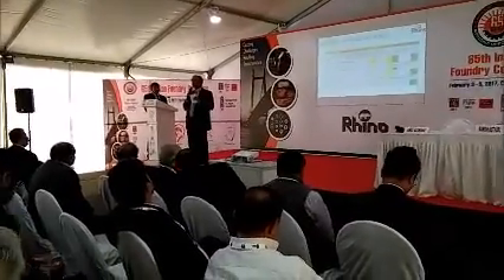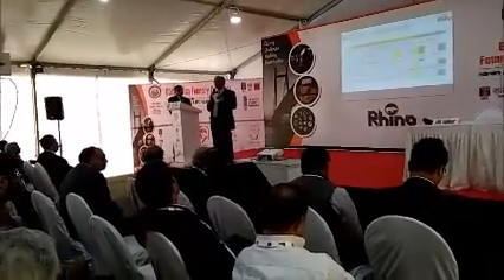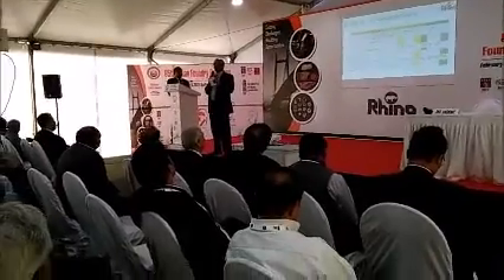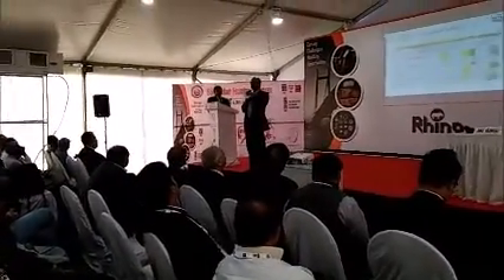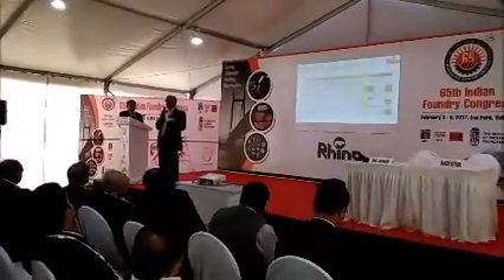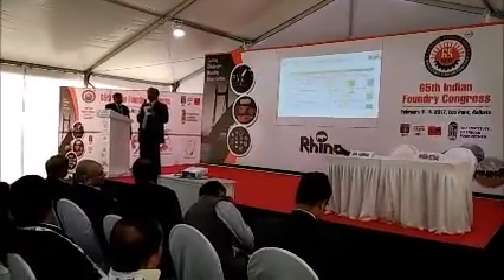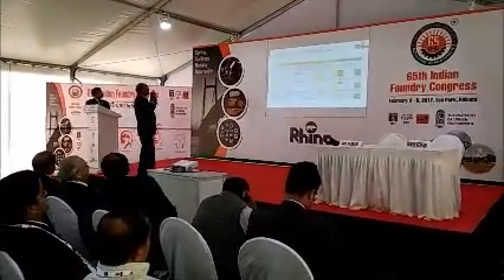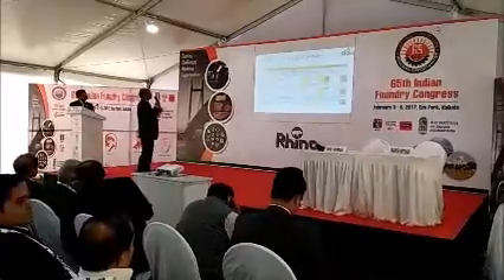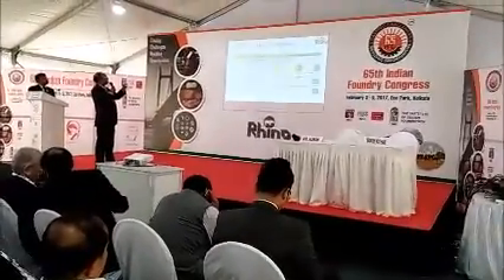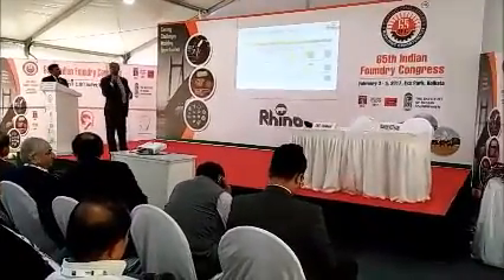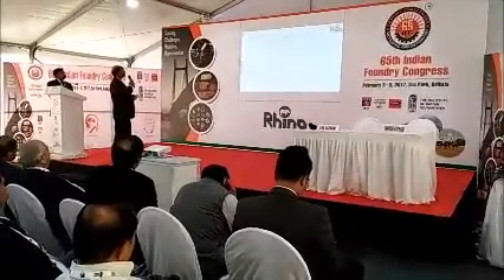You don't want to cross 500 KVA; if it goes to 501, you will get an SMS. Automatically, 4 people will get the SMS, and they can reduce the power on any equipment or the furnace can be reduced. So you don't overshoot your maximum demand also. By improving power factor from 85 to 95, you can save almost 200 kVA in your billing.